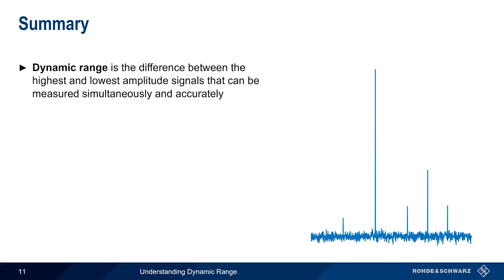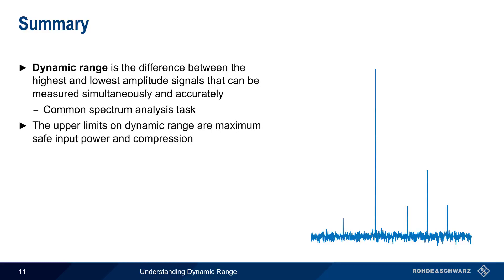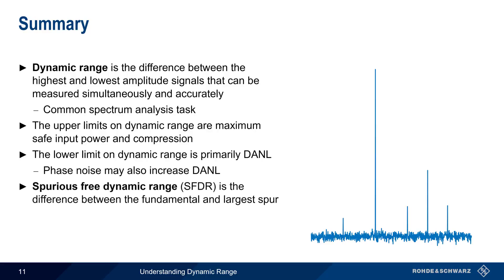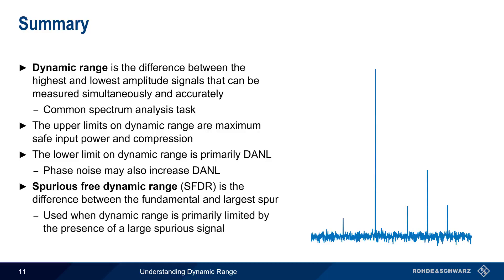Let's end with a brief summary. Dynamic range in a spectrum analyzer is defined as the difference in dB between the highest and lowest amplitude signals that can be measured accurately and simultaneously. This is a common task in spectral analysis, and therefore dynamic range is an important figure of merit for spectrum analyzers. On the upper end, dynamic range is limited both by maximum safe input power, as well as by compression, which reduces amplitude accuracy. On the lower end, dynamic range is limited by the analyzer's noise floor, or DANL, which represents the minimum signal amplitude that can be measured. Note too that the presence of phase noise may also increase DANL in some cases. A special case of dynamic range is spurious-free dynamic range, which is the difference in amplitude between a fundamental signal or carrier and the largest spurious signal. Spurious-free dynamic range is measured in units of dBc, and is most often used when dynamic range is limited by the presence of a large spurious signal, rather than by noise or compression.